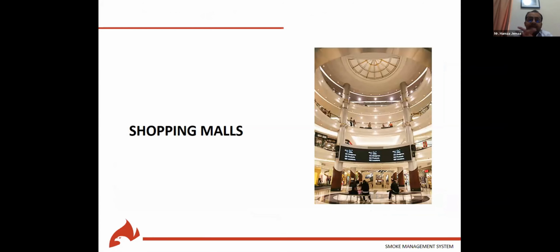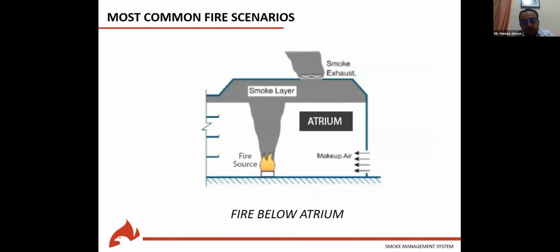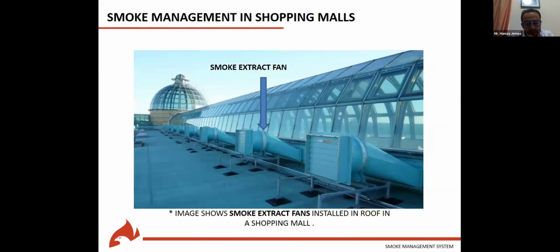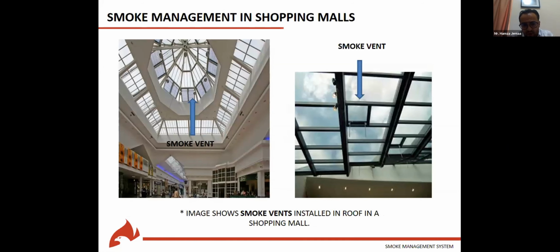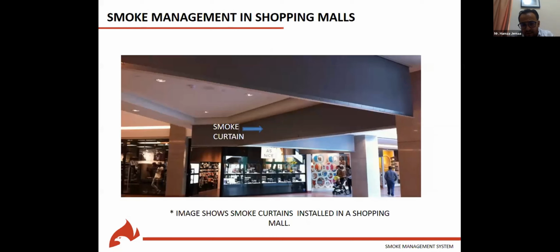Another application of smoke control system is inside shopping malls. And as you know, in shopping malls we find atriums. Here is a fire scenario inside atriums. There is an illustration of smoke exhaust fans and the makeup air, and the design should consider all these inputs. Here, a picture of the extraction fan on top of the atriums. Another picture of a smoke exhaust window on top of atriums. Smoke curtains are used to prevent the smoke from entering the communicating spaces and allow the smoke to be directly diverted to the extraction point, which is the smoke extraction fan on top of the atrium.